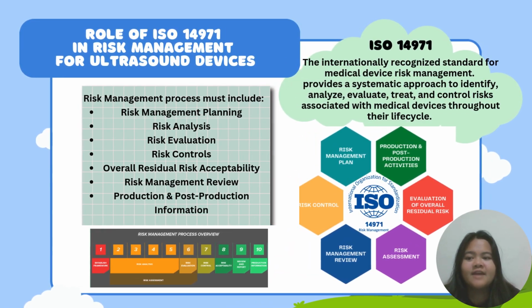Today I would like to discuss the role of ISO 14971 in risk management for ultrasound devices. ISO 14971 is the internationally recognized standard for medical device risk management. It provides a systematic approach to identify, analyze, evaluate, treat, and control risks associated with medical devices throughout their life cycle.